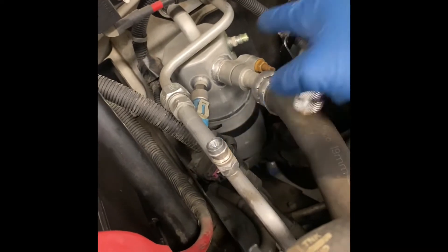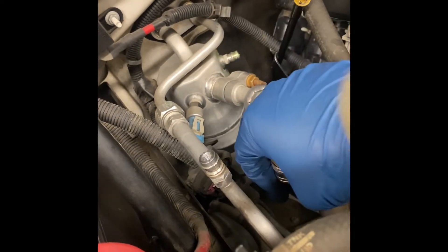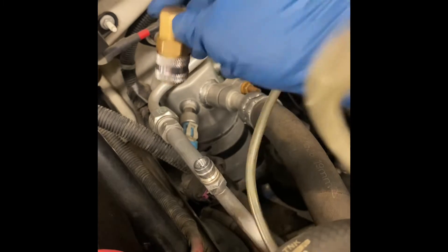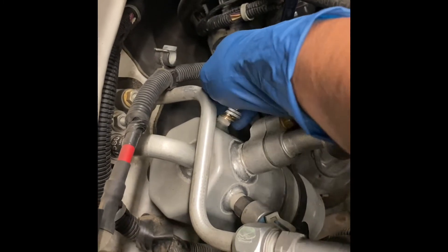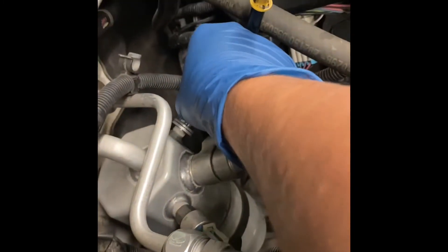As you can see there are two connectors, one on that side and one right here. Let's say you're not able to determine which one's high or which one's low — I know for a fact this one is high. This connector here is a low connector and should only be connected to the low side. But look what happens if I try to fit it in the high side — it's not going in at all, even with pressure. That's how you know this is the high side.